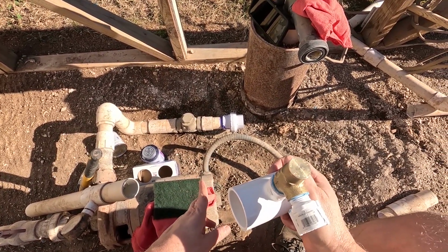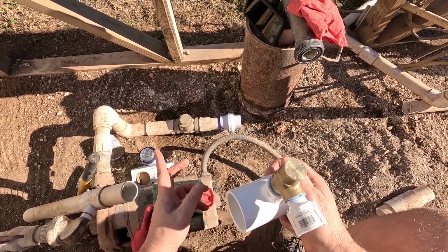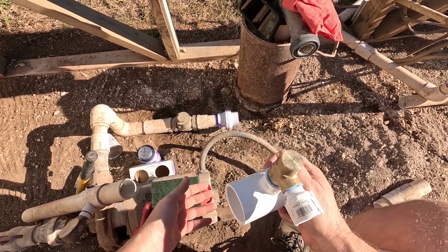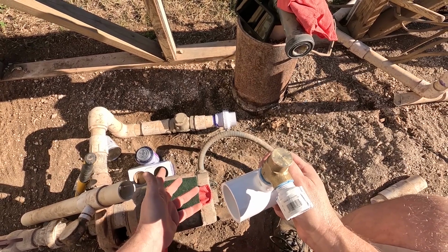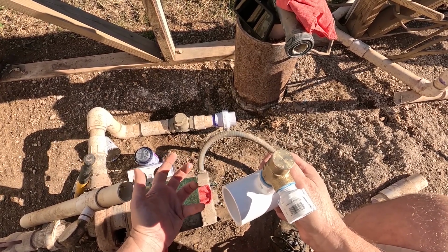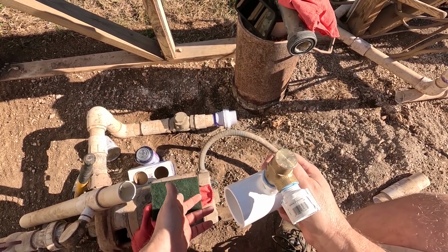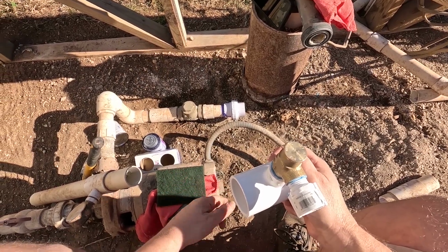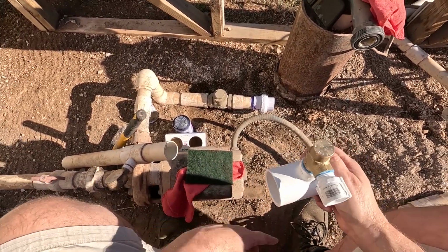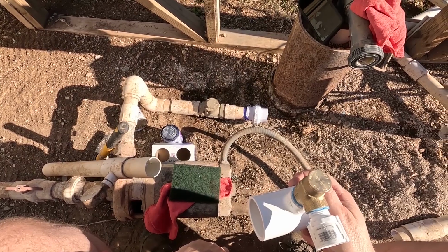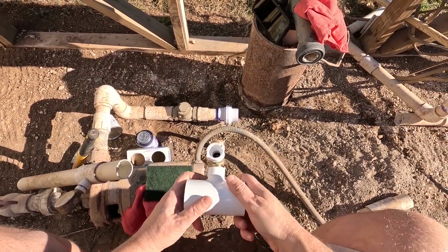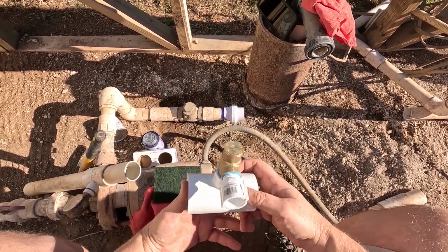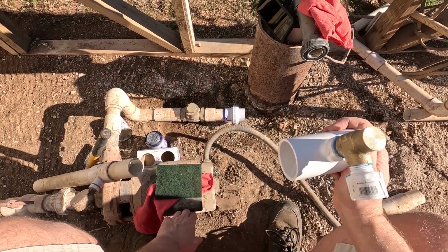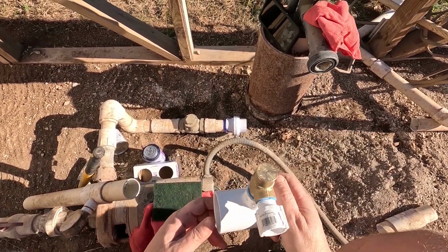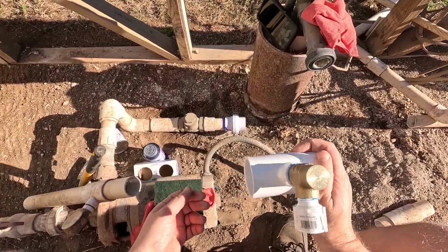I'm not sure why it doesn't, because the problem is if you turn the sprinklers on, your heads are open, so it's okay. But if you have a head or a circuit fail and this pump's just sitting there pumping with no place for the water to go, these things will create some pressure. So I'm worried about blowing out a line. While I've got it all apart, it's standard practice with an irrigation pump like this to have a relief valve, or some way for pressure to relieve itself. So we're going to add this in there.